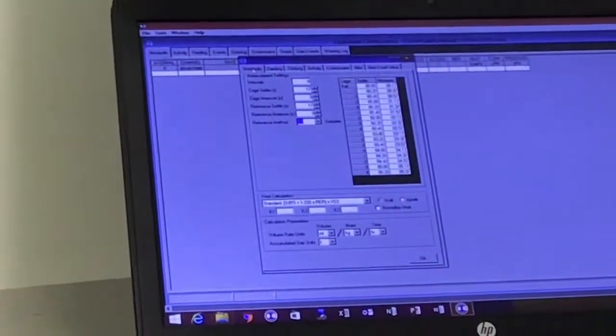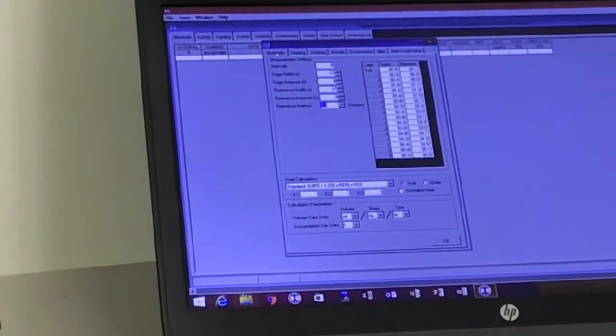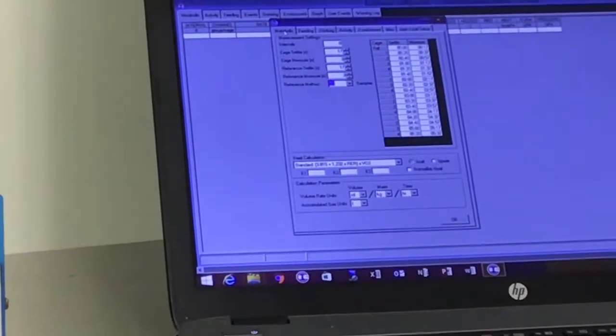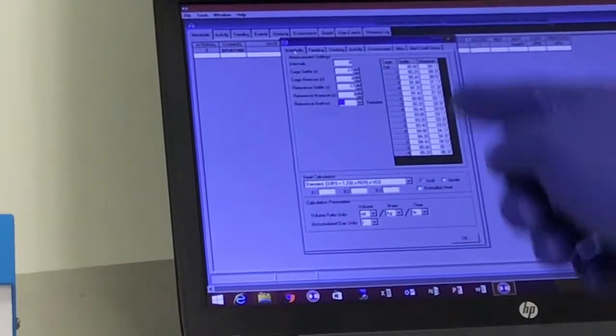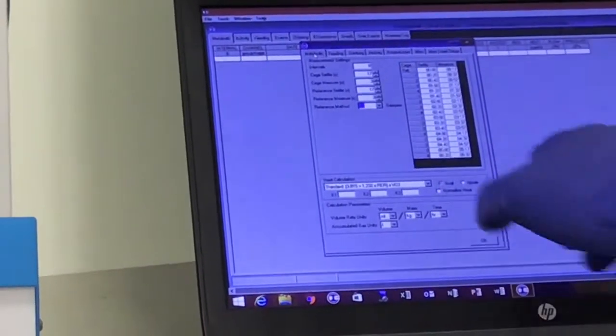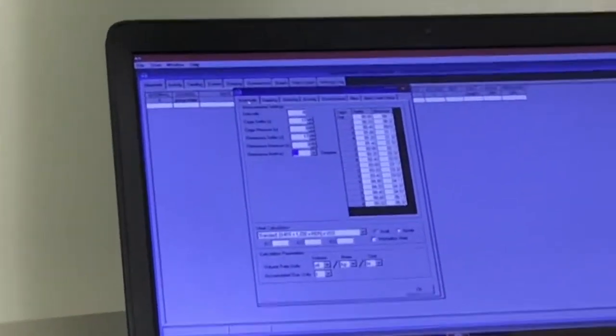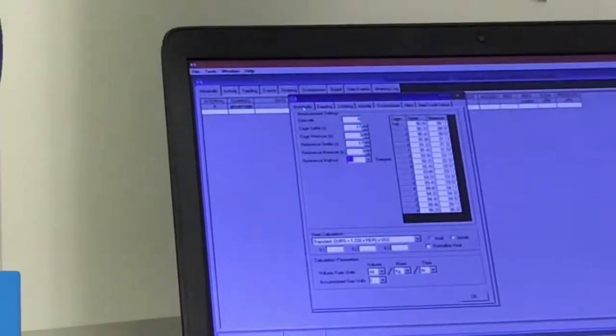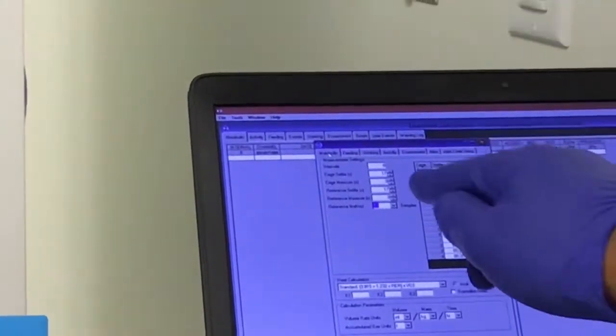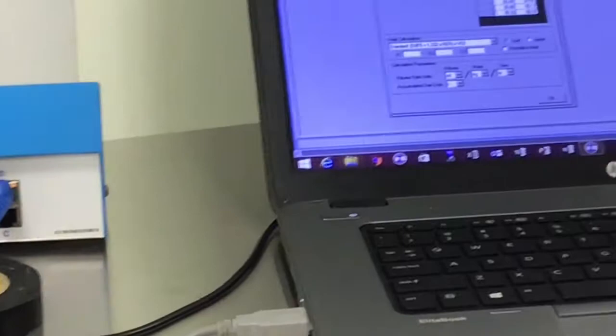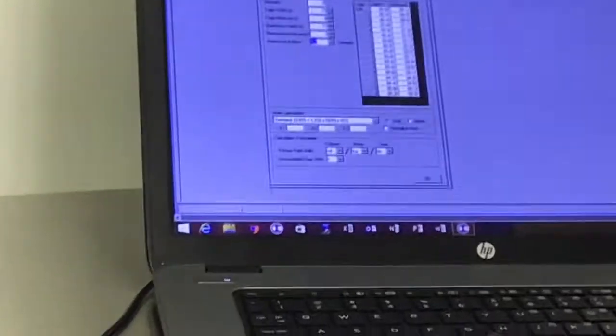Here, you decide how long it takes to switch from one cage to another cage. How long does it take to measure from one cage? Your system is very fast, 20 seconds for each cage. So if we run a 4-cage experiment, every minute and 20 seconds I'm going through 4 cages, so I'm getting a lot of data. What happens if I change this cage measure and make it, for example, 1 second? It's going to shorten by 2 seconds on each cage, but is it enough time to actually measure?